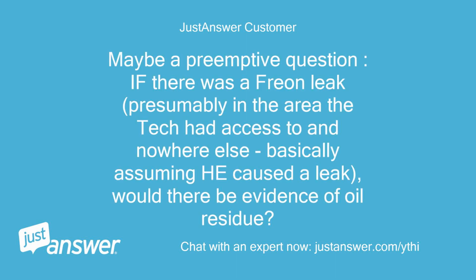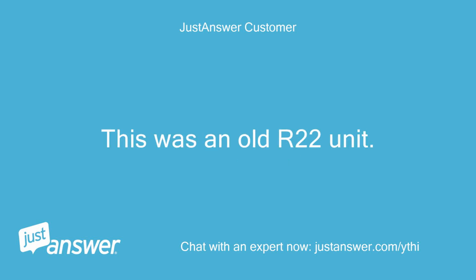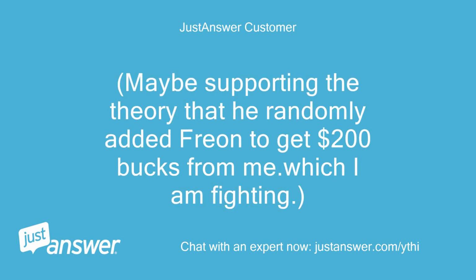Maybe a preemptive question: if there was a Freon leak, presumably in the area the tech had access to and nowhere else, basically assuming he caused a leak, would there be evidence of oil residue? I had a leak on my old system, granted it was bad, but there was oil all over. This was an old R22 unit. I ask this because I see zero evidence of oil residue. Anywhere. Maybe supporting the theory that he randomly added Freon to get $200 from me. Which I am fighting.